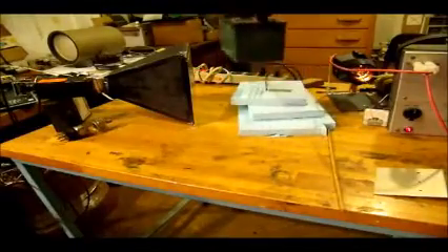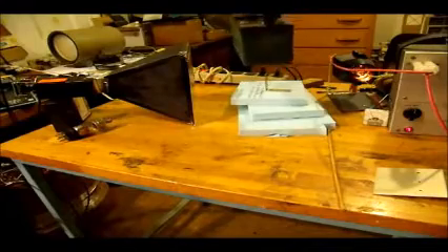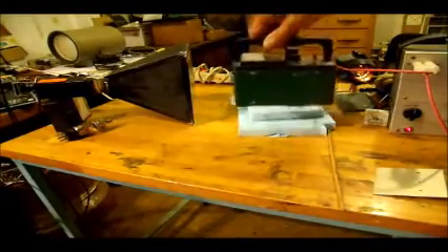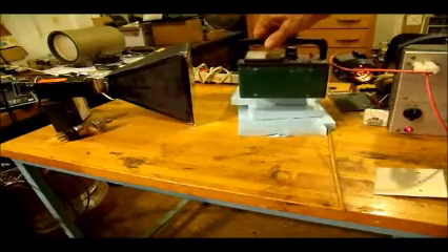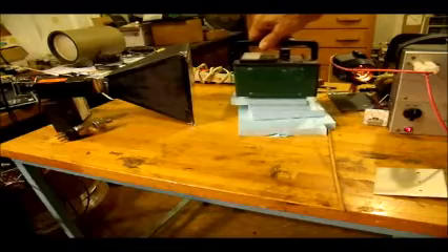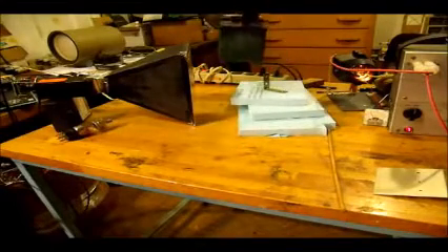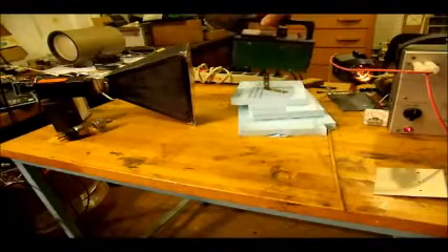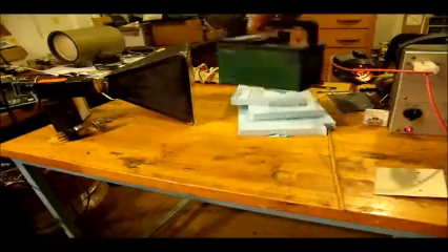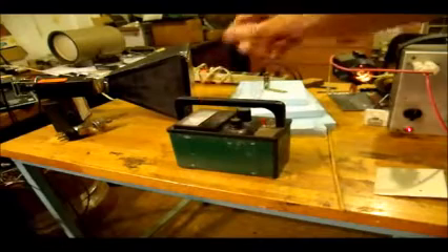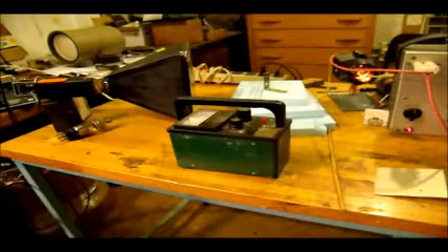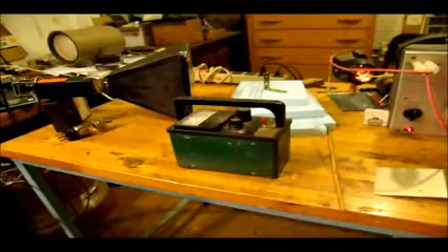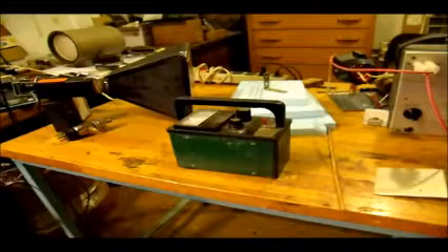If I turn on the survey meter, we don't get any reading. Just a heck of a reading when we get into the beam. But outside the beam, you can see that that plastic shield really does a good job of keeping it down. We're just reading background here, but we get just into the beam a little bit. My goodness. It's strong. It's probably a few hundred milliroentgen per hour rate on it. Maybe more than that. I'd have to calculate it to see. Okay, I'm going to shut this off so that we don't overheat the tube. And it looks like our tube is good.